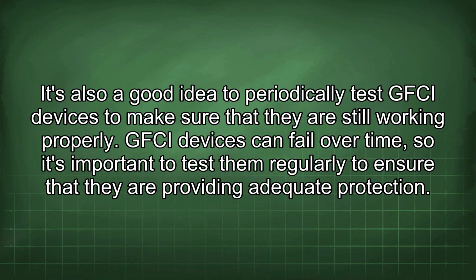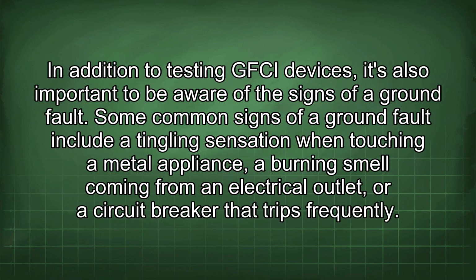It's also a good idea to periodically test GFCI devices to make sure that they are still working properly. GFCI devices can fail over time, so it's important to test them regularly to ensure that they are providing adequate protection. In addition to testing GFCI devices, it's also important to be aware of the signs of a ground fault. Some common signs of a ground fault include a tingling sensation when touching a metal appliance, a burning smell coming from an electrical outlet, or a circuit breaker that trips frequently.